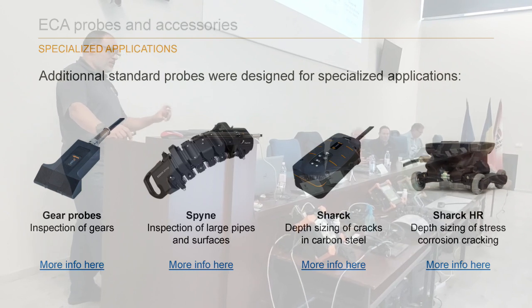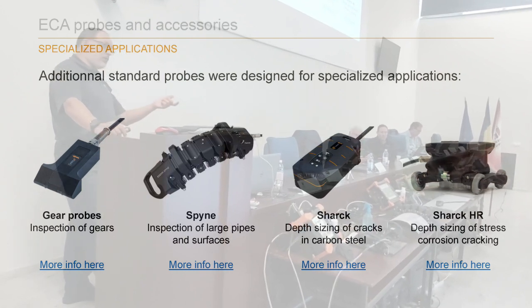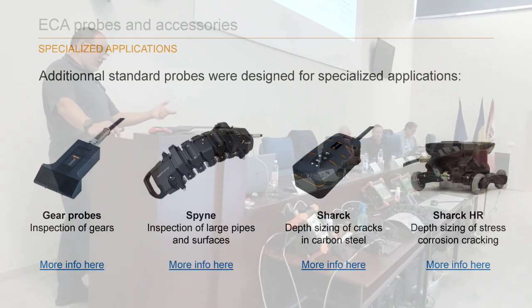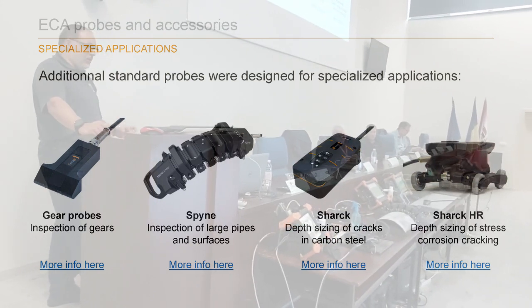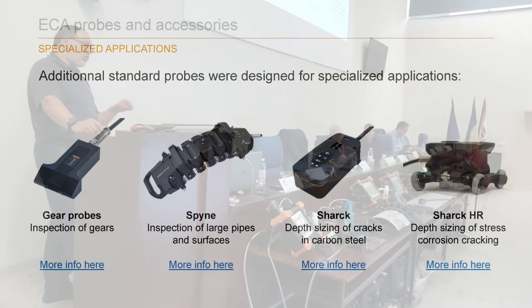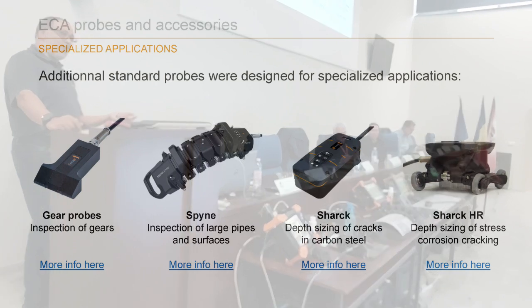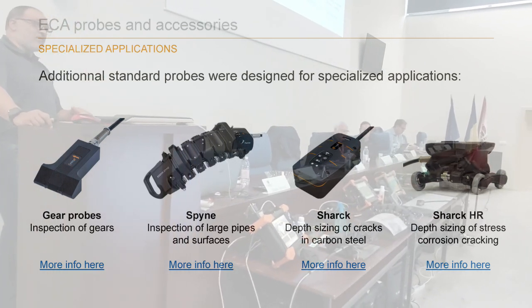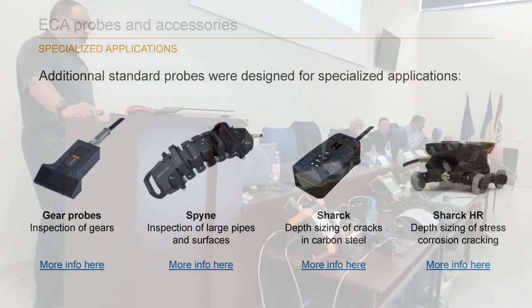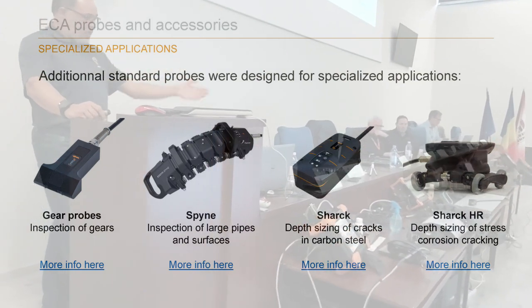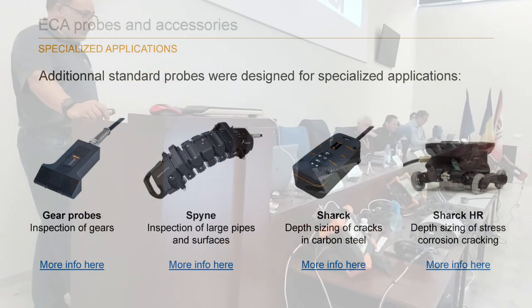This is an evolution of eddy current array we call TECA, tangential eddy current array. That allows you not only to size the length of the defect of the cracks, but also to size the depth of the crack, which is the most important part. And the Sharck HR, as I said, is here today available.